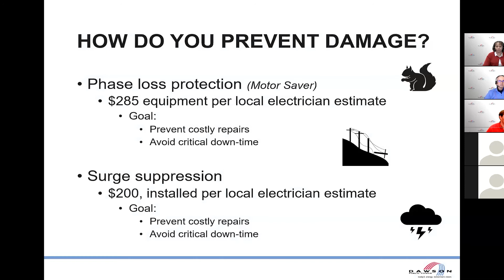Another type of failure that we see out in rural America, of course, is transients. To protect from those type of incidents is a surge suppressor. This is typically installed right at the motor, to protect from lightning damage, protect from some other failure within the actual irrigation system itself. Another fairly reasonably priced insurance policy, if you will. So a couple of different ways. If you don't have this type of protection on your systems, highly recommend talking with your electrician or your irrigation equipment provider to possibly add this type of equipment.